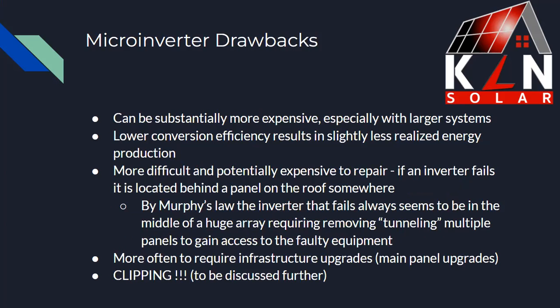What are some drawbacks of microinverters? First and foremost, the elephant in the room: they can be substantially more expensive, especially with larger systems. If we're talking a system with 50, 100, or 150 panels, you have 50, 100, or 150 inverters — that cost goes up quick. You typically have a lower conversion efficiency and more duplicity of equipment, resulting in slightly less realized energy production, meaning less of the energy your system produces is actually available for your home to use.